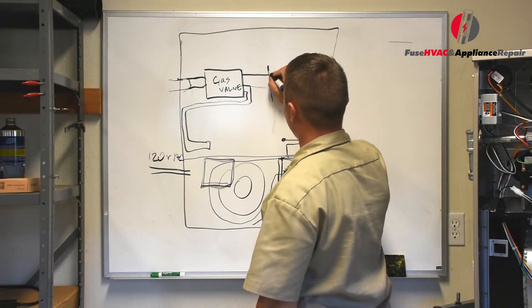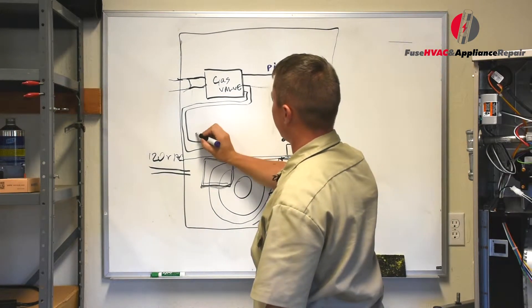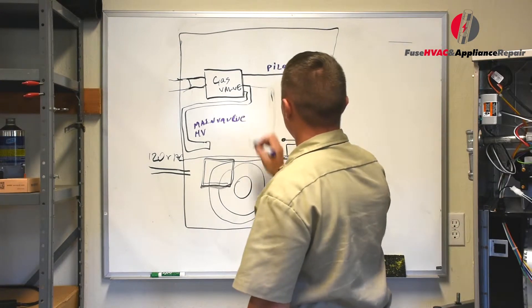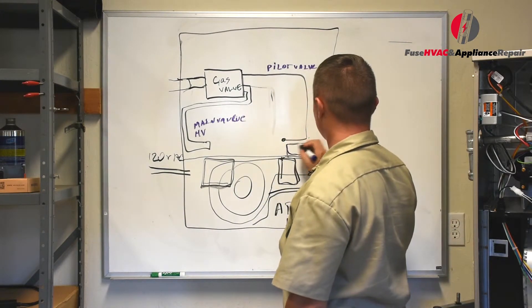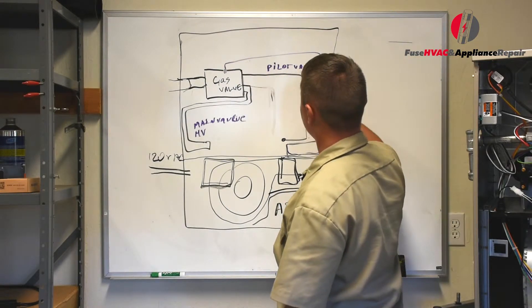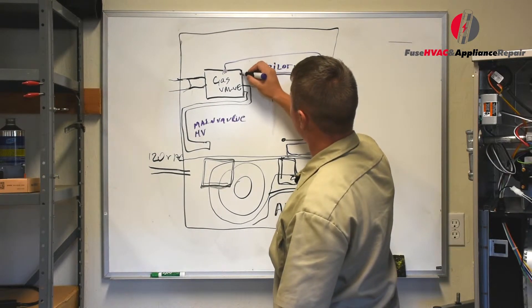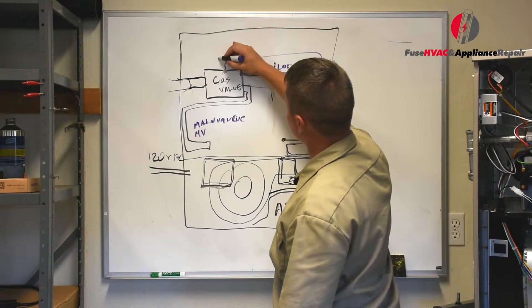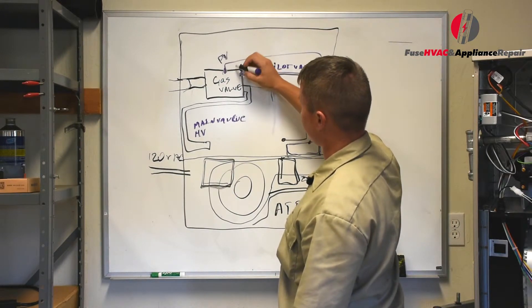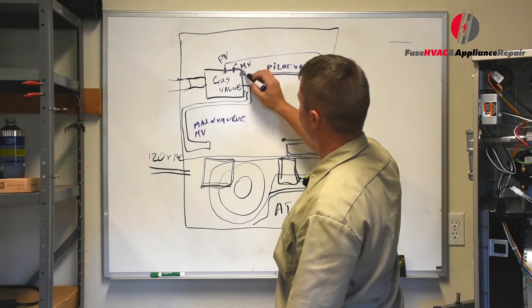This small tube is called the pilot. This is the pilot valve pipe, and this is the main valve — MV, or main valve. The gas valve is energizing first the pilot valve, and the second one is energizing the main gas valve — MV — and PV, pilot valve. Usually you will see these signs on the gas valves, and they also have one common contact: a pilot valve contact, common contact, and main valve contact. All of these wires go to the ignition module.